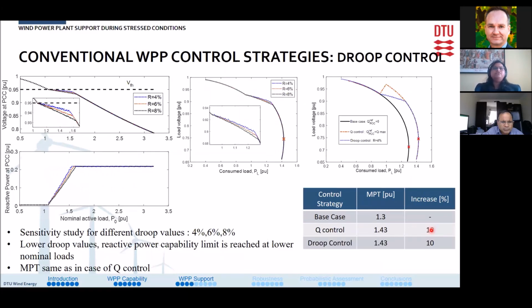So next we go into the droop control strategies. Here also we did a sensitivity study for different values of droop, 4%, 6%, and 8%. If you see the performance of the three droop values, it is more or less comparable. The only difference is that for lower droops, the reactive power capability limit is reached at a lower nominal load. However, if we compare it with the previous Q control strategy, we can see here that the maximum power transfer still remains the same as in the case of Q control strategy.